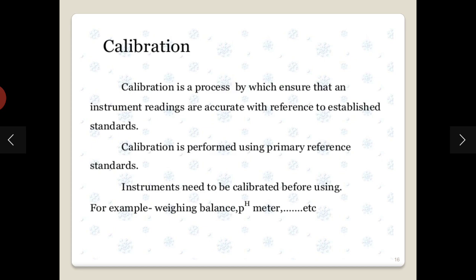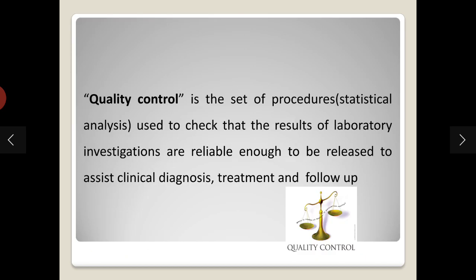Calibration is a process that ensures instrument readings are accurate with reference to established standards. It is mainly done to align the instrument and is performed using primary reference standards. Calibrators are commercially available materials used according to manufacturer instructions. The instrument should be calibrated before running patient samples.